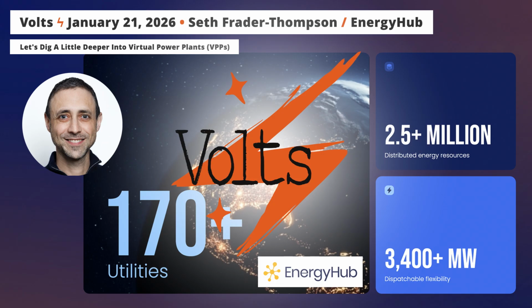In many ways, it's the same problem as you have at the transmission level. Somebody does an analysis and figures out what the maximum coincident demand for power is going to be on this piece of wire that stretches through this neighborhood, or how big does this service transformer need to be to serve the 4 homes behind it. So if you put something in 10 years ago and you still have plenty of extra capacity, great, until that thing wears out it'll just keep doing its job. But if load grows behind that thing, at some point you've got to replace it. So the question is, what if you don't?